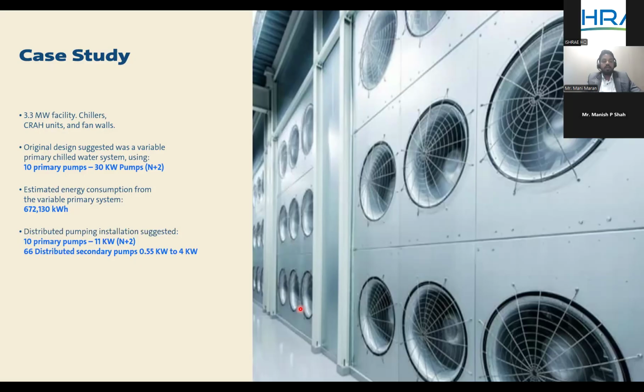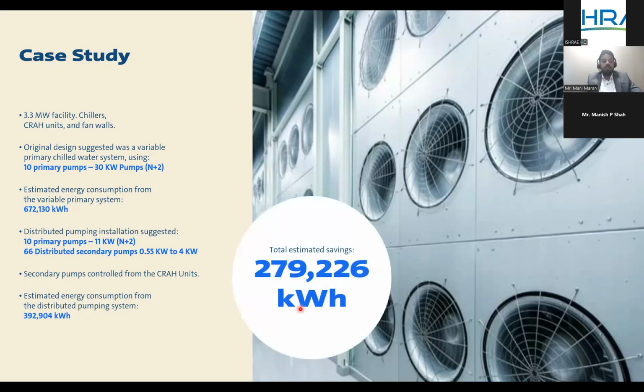After adopting the distributed pumping design, the energy consumption is around 392,000 kilowatt hour, and the savings are around 279,000 kilowatt hour, which is approximately 40 to 50% energy saving on the pumping power consumption. Apart from this, managing the delta T to a better level will bring much more efficiency on the chiller side, which will help us improve the kW per TR as well as reduce the PUE in total.